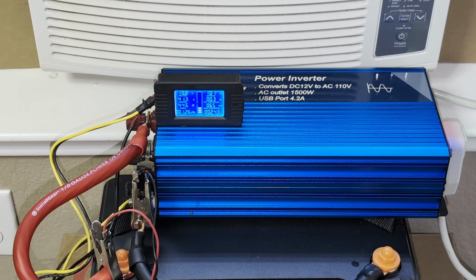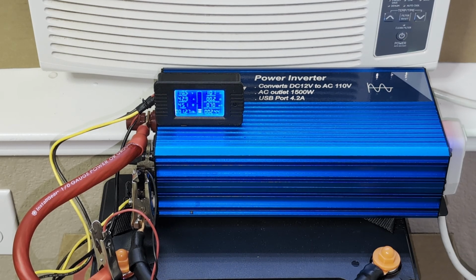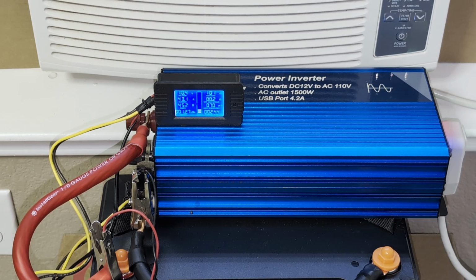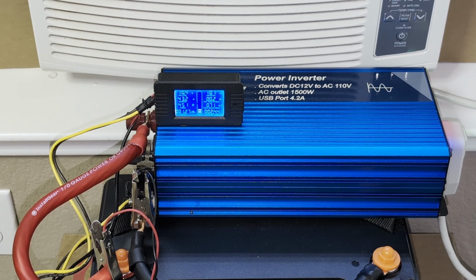If you can see on the battery monitor, we've already surpassed 100 amp hours. We're fixing to hit its max kilowatt hours, which would be 1.28, but it's at 1.26 and still has a little bit of power left. Any minute now the battery or the inverter is going to kick off for low voltage, but the battery says it's actually 100% used, so we've gotten everything we expect out of it. I'm just going to let this finish up. Well, there it goes — it's beeping. I'm going to go ahead and kill it, but the capacity test is good. It definitely lives up to its ratings.